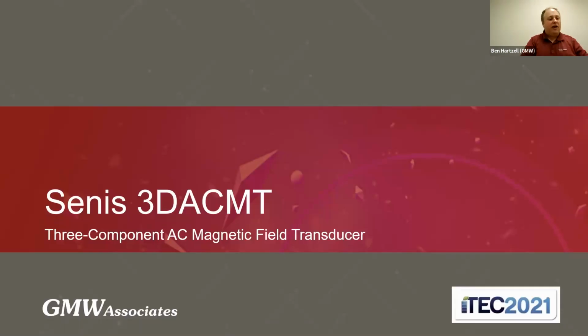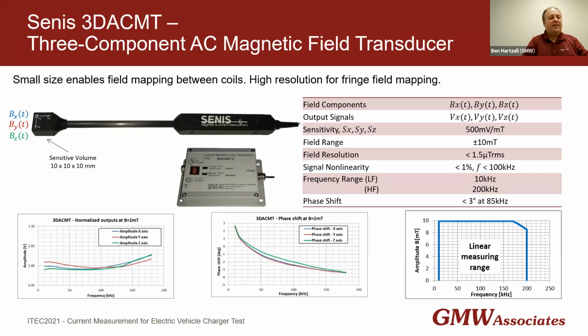There's one more instrument I want to talk about today, but it's not a current probe. We're actually going to mention a magnetic field transducer here. It's a 3-component AC magnetic field transducer. The Senis 3DA CMT is a 3-component AC magnetic field transducer. What that means is we're measuring BX, BY, and BZ, all 3 vector components of the magnetic field within the same sensitive volume of 10 by 10 by 10 millimeters. For each of BX, BY, and BZ, you have a separate output of VX, VY, VZ. That's a voltage proportional to the field.